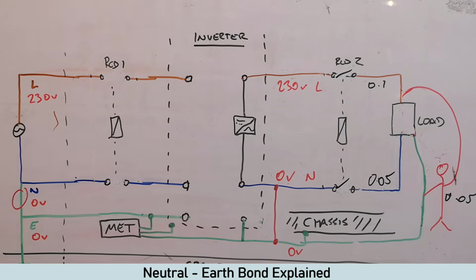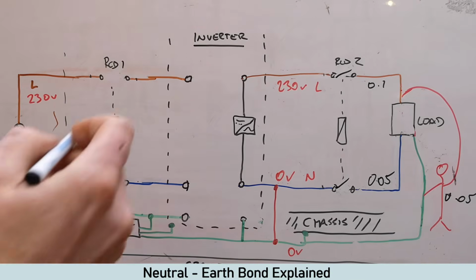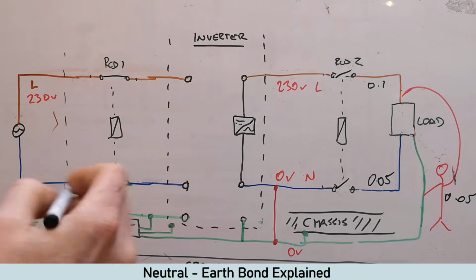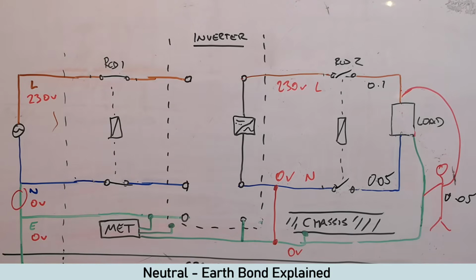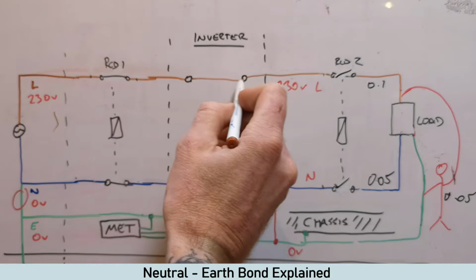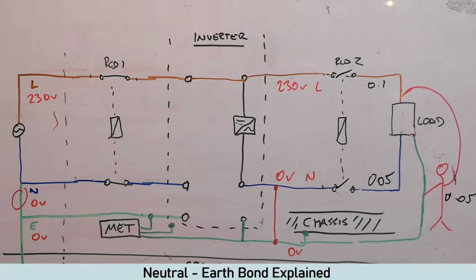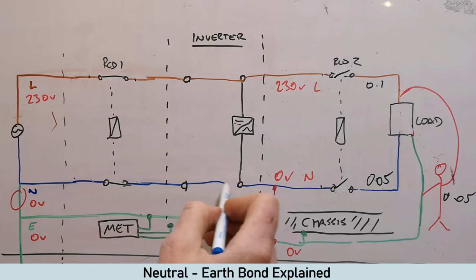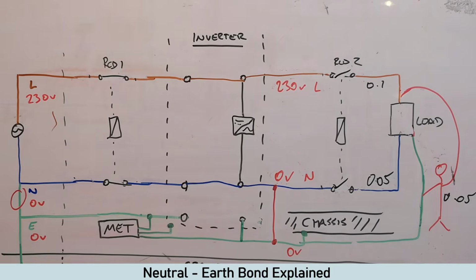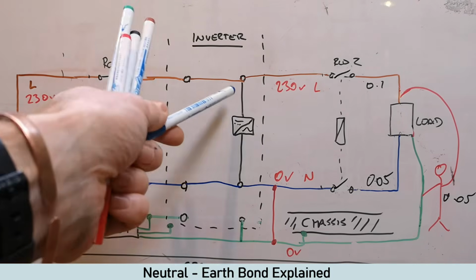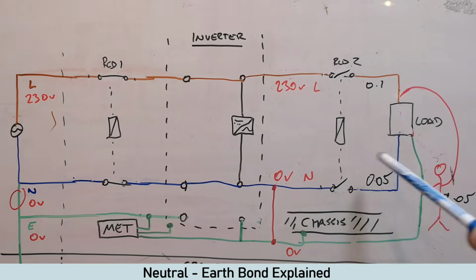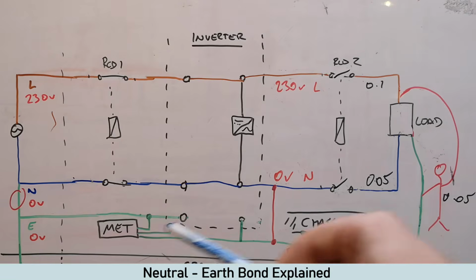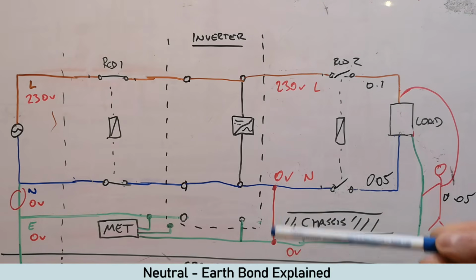So now you're probably thinking, happy days, problem solved, no issues. But what happens now if you put the hookup back on? So let's put hookup back on and see what happens. So that'll link to there, then the neutral links to there. So like before, obviously hookup's on, RCD's on, the internal bypass is on. Obviously nothing happens here because it's still 230 and 0, so power's going to flow around lovely jubbly. The only difference is this link here.